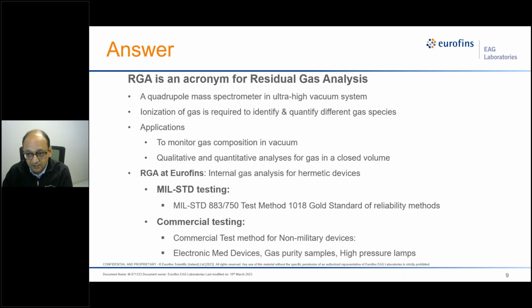And as Frona said earlier, this technique was developed in the 1970s and especially converted into a very specific test method called MIL Standard 883-750 test method 1018. This test method became over the years a gold standard for hermetic devices, which are microelectronics devices as well as medical implants. We have to follow that test method when we are doing MIL standard testing. But if we deviate from the parameters defined in that test method, then we would term that testing as commercial testing.